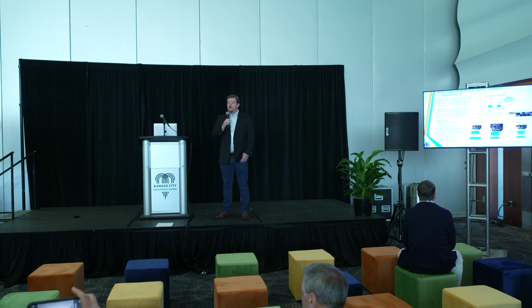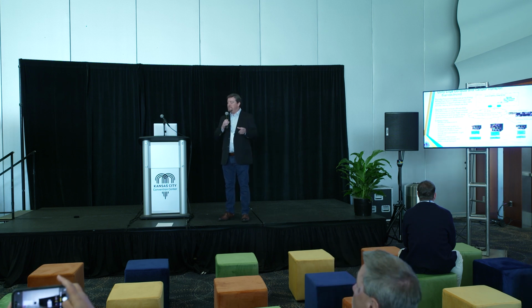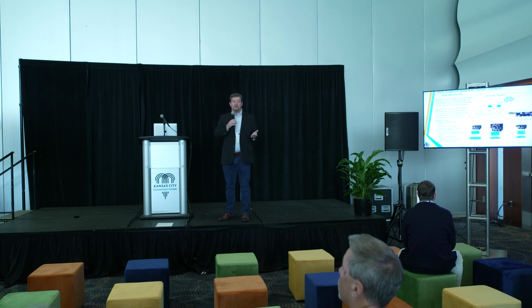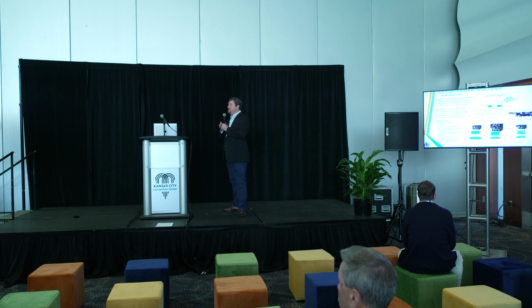So as the amount of DER starts to increase on the grid, and the volatility of optimized set points increases on the grid, it becomes tougher for the EMS to update those controllers on a frequent enough basis. So the EMS can be something of a bottleneck, and the main point we were doing with these edge applications was to ease that bottleneck, push some of that decision making to optimize the controllers out to the edge, and that's what those applications did.